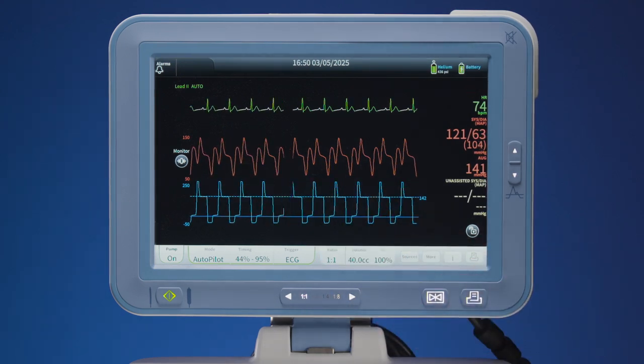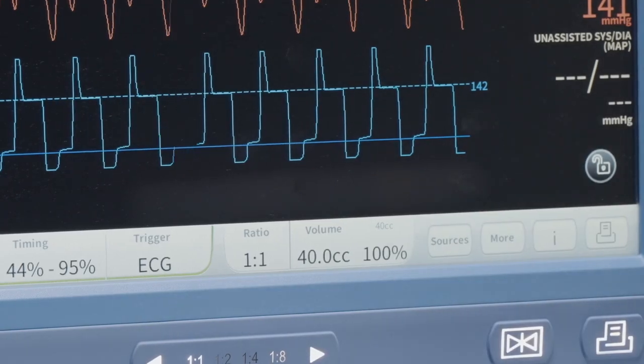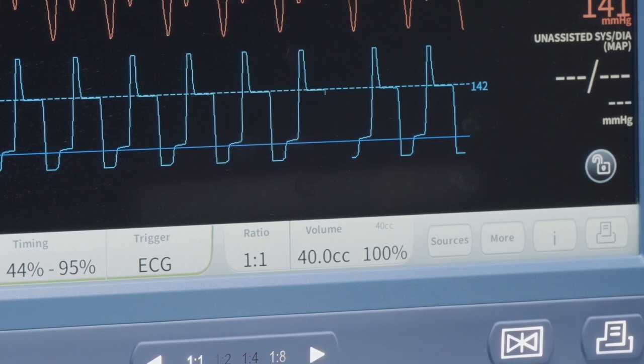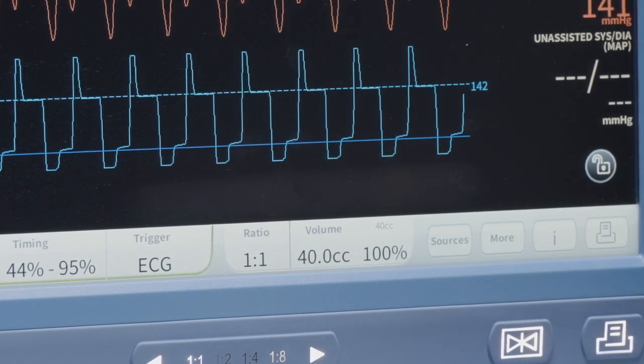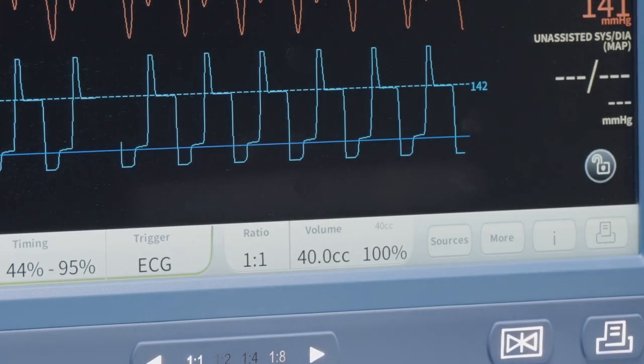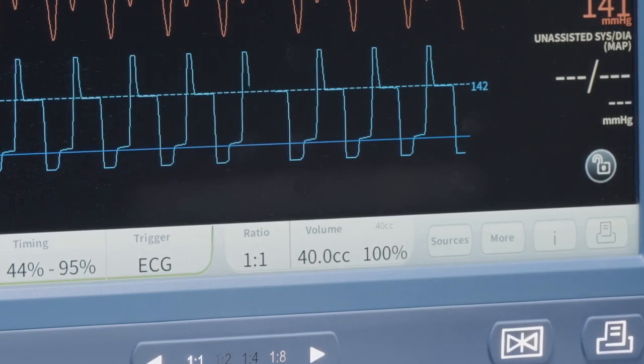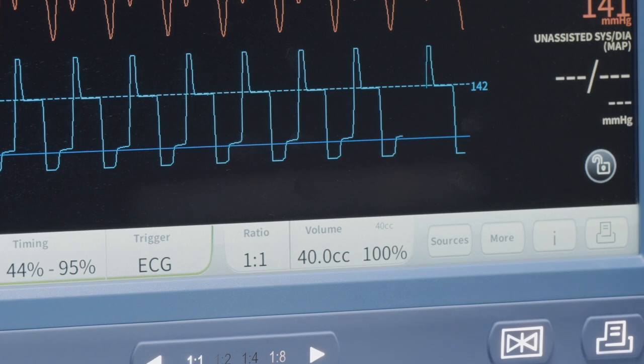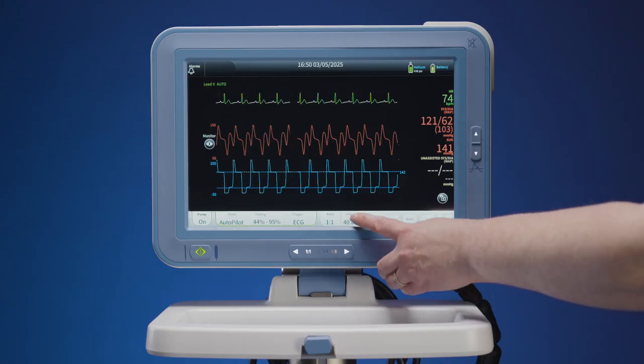The AC3 Optimus IABP automatically sets the volume from the IAB connector. The connectors come with each IAB in the balloon insertion kit. When the connector is attached to the pump, the volume will be displayed on the action bar. However, when volume changes are required, the AC3 Optimus IABP lets you set the precise volume to be delivered to the IAB in 0.5 cc increments. The user cannot set inflation volume greater than the balloon's maximum capacity.